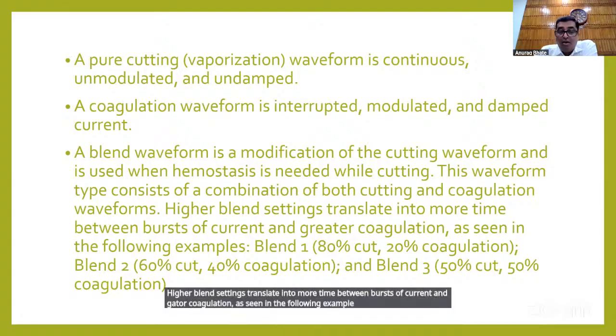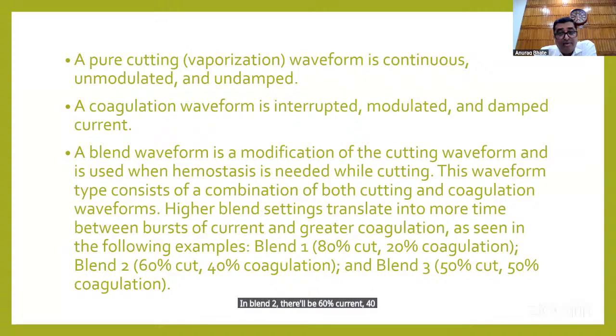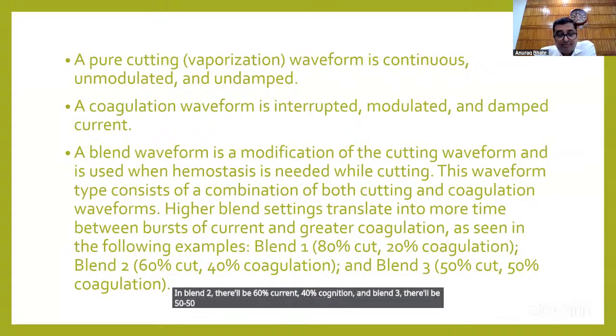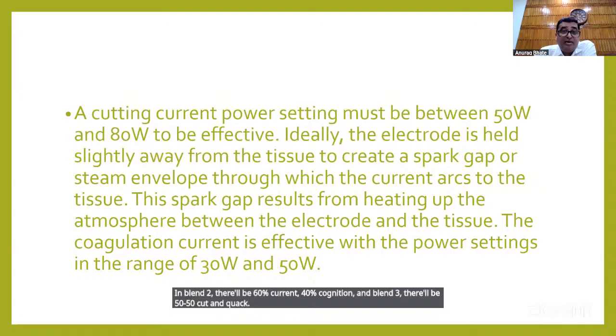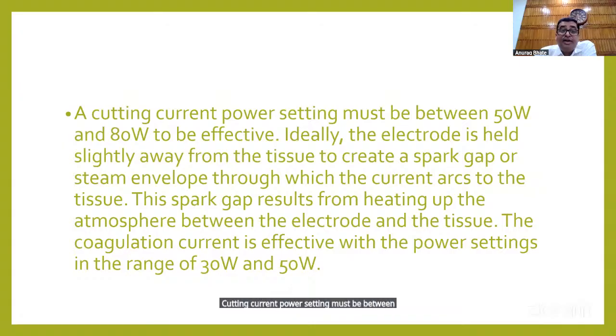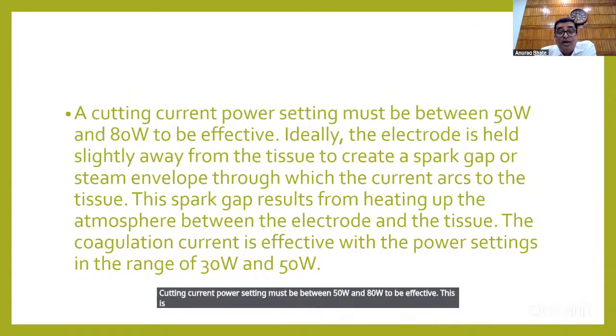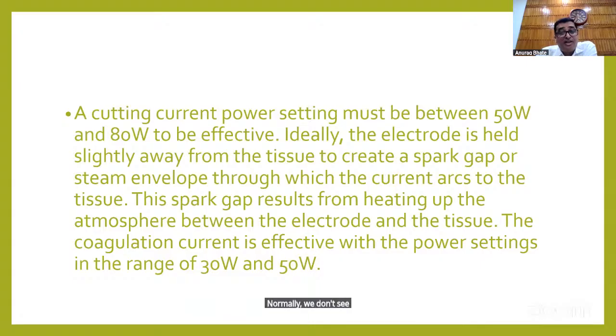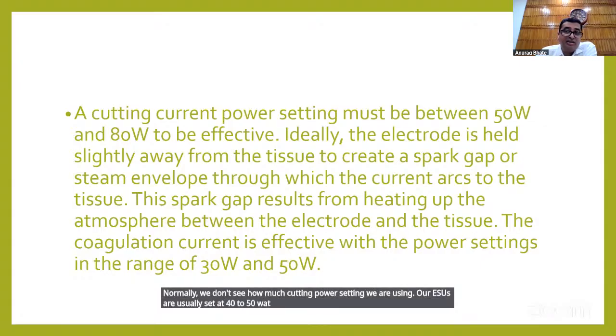In blend 1, sorry, there will be 80% cut current, 20% coagulation. In blend 2, there will be 60% current, 40% coagulation. And in blend 3, there will be 50-50 cut and coag. A cutting current power setting must be between 50 watts and 80 watts to be effective. This is very important. Normally, we don't see how much cutting power setting we are using. Our ESUs are usually set at 40 to 50 watts. 40 is adequate for what is required. 50 is what we normally keep if required. But if you are doing a hysteroscopic myoma resection, we can go up to 100 and 110.